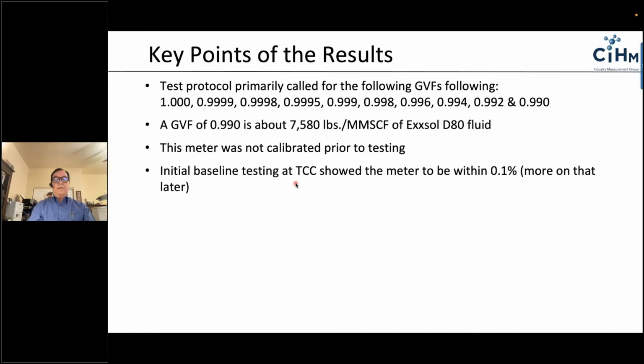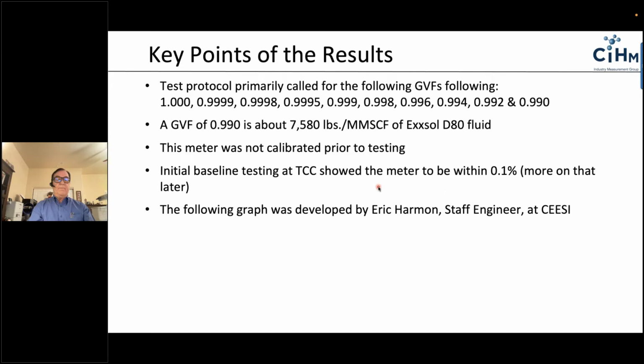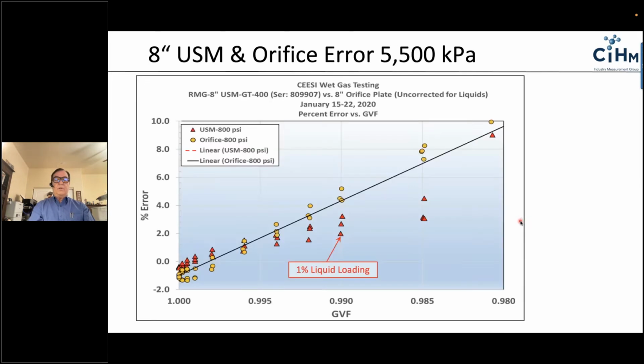It was baseline tested at TransCanada and shown to be within about 0.1% of the lab. And I'll show you data on that in a moment. The following graph was developed by Eric Harmon. He's the staff engineer at CEESI. The idea is to understand what is the meter's performance relative to an orifice meter. So what we have downstream of the ultrasonic meter was an 8-inch orifice meter.